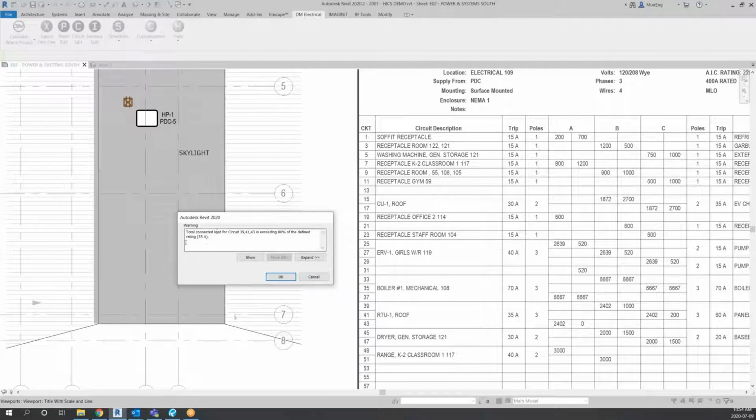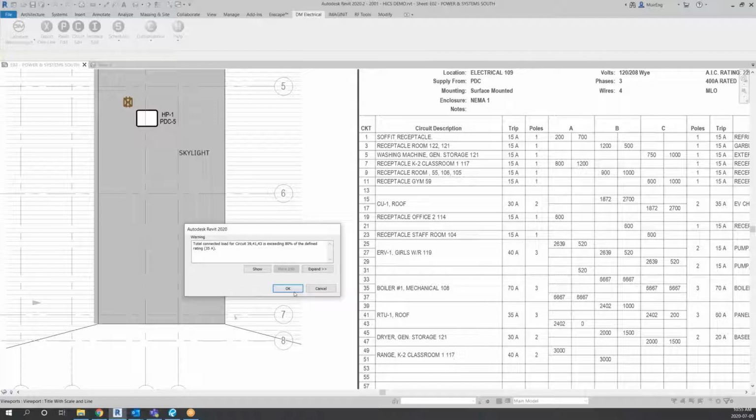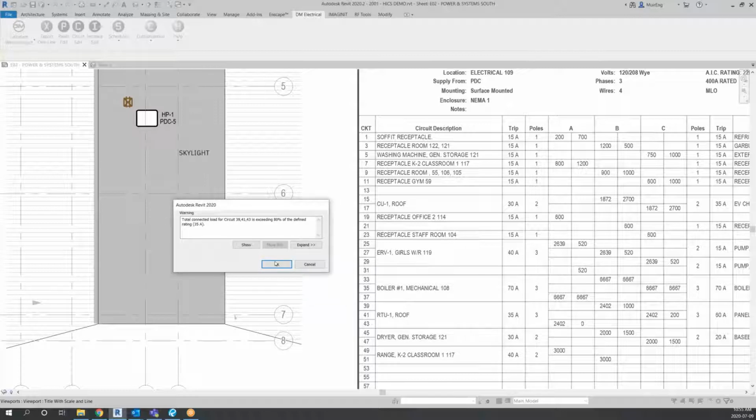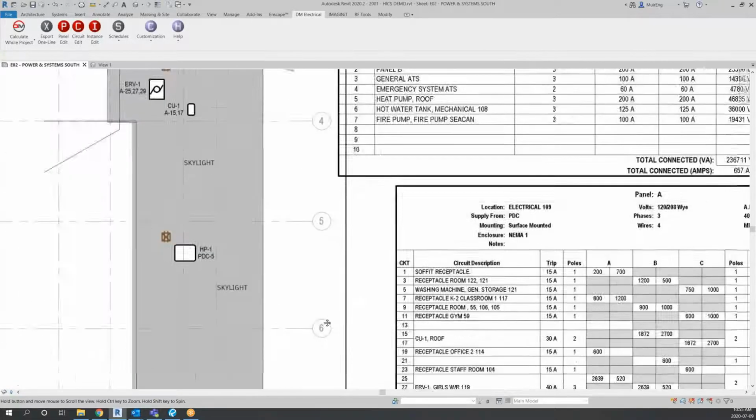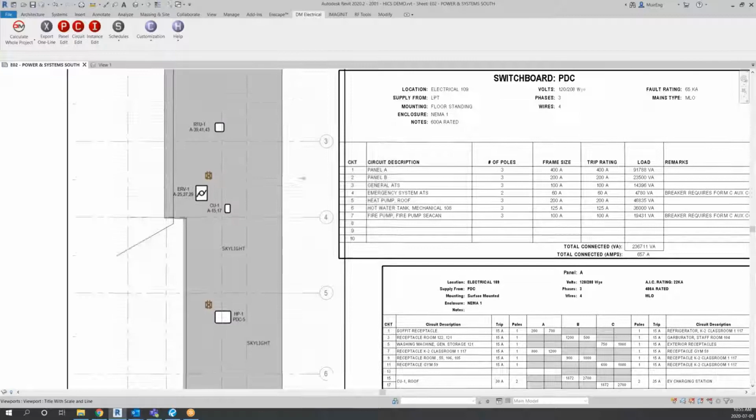Now, I might have a problem with my setup of that part because really it shouldn't be giving me this warning. So I probably have a mismatch between MCA and FLA and MOP on the setup of that part, what's leading to this. But anyway, Revit's telling you there's something you better look out for because there may be an issue. So we would investigate that and likely just update our family.